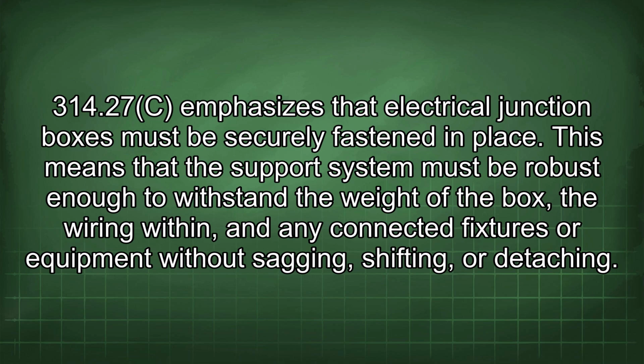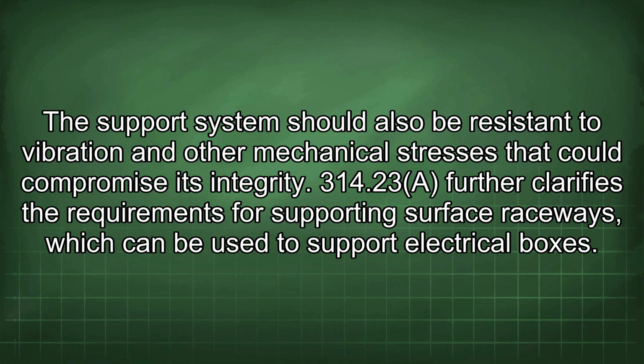314.27c emphasizes that electrical junction boxes must be securely fastened in place. This means that the support system must be robust enough to withstand the weight of the box, the wiring within, and any connected fixtures or equipment without sagging, shifting, or detaching. The support system should also be resistant to vibration and other mechanical stresses that could compromise its integrity.